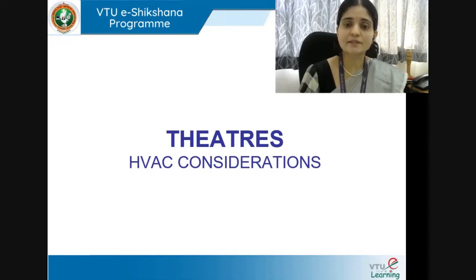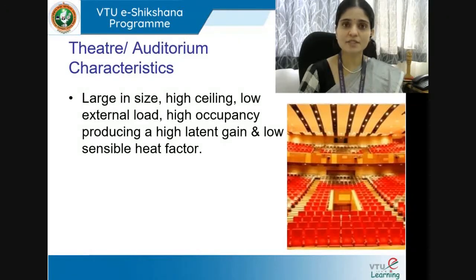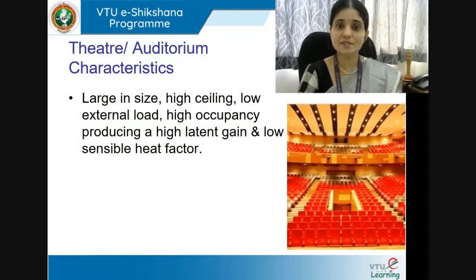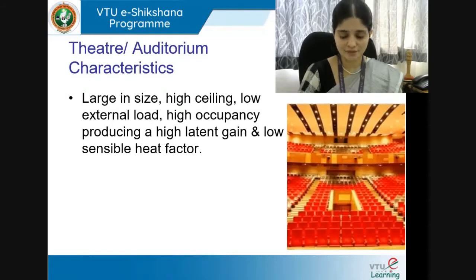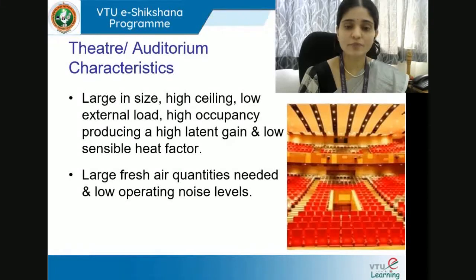Moving on to theatres and auditoriums. Theatres are spaces of large gathering, with many people at a given point of time, and spatially they are large in volume with high ceilings. There is definitely low external load but high occupancy load, producing high latent gain — opposite to what we saw in server rooms. A suitable HVAC system must account for large fresh air quantities, and operating noise levels must also be minimized.